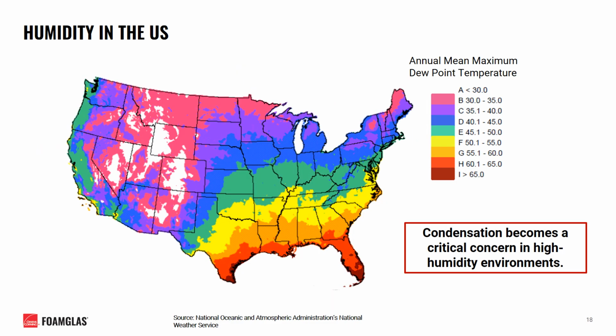Another piece to consider when designing your chilled water system is the geographic location of your project. Different parts of the country will be subject to different temperatures and relative humidity, resulting in different vapor pressures. Here we have a rough illustration of the annual mean maximum dew point temperatures that various parts of the country typically experience. Condensation becomes a critical concern and a more likely problem to encounter in high humidity environments where there exists a much higher vapor drive from the ambient air towards a cold pipe surface. As a quick note, I'd like to point out that this map shows the average max dew point, but does not showcase extreme conditions that individual locations may experience.